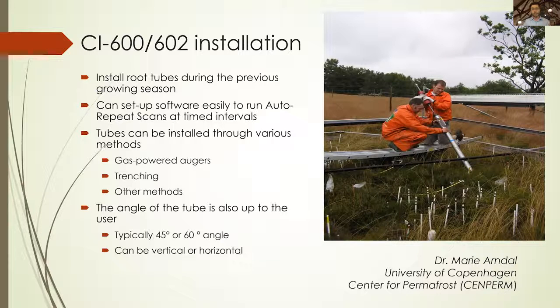So there are many methods of installation I also want to mention. We do typically suggest using a 45 or 60 degree angle. This is a little bit for historical reasons, and it also helps keep out things like rain and other environmental factors. But this instrument works either vertically or horizontally as well. I'll show you a bit later in the presentation that you can install it in a lot of very ingenious different methods.